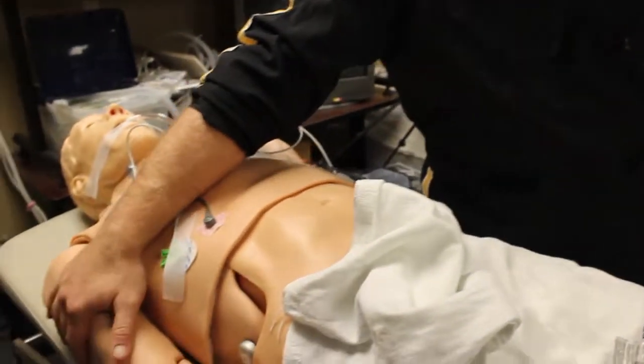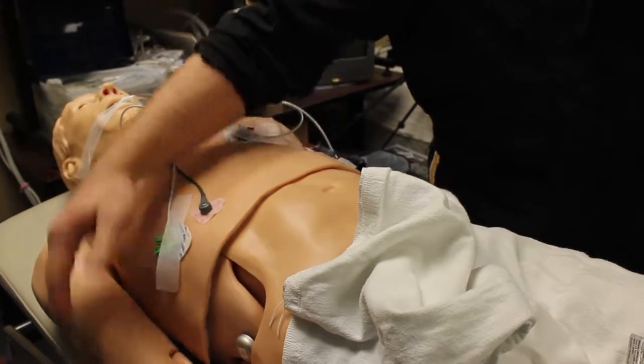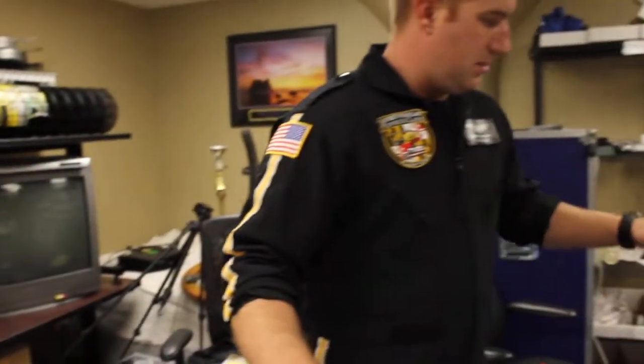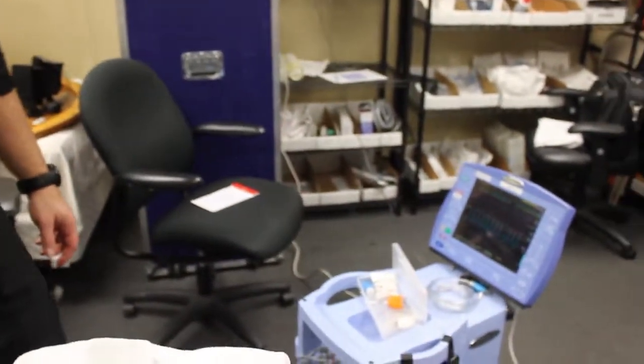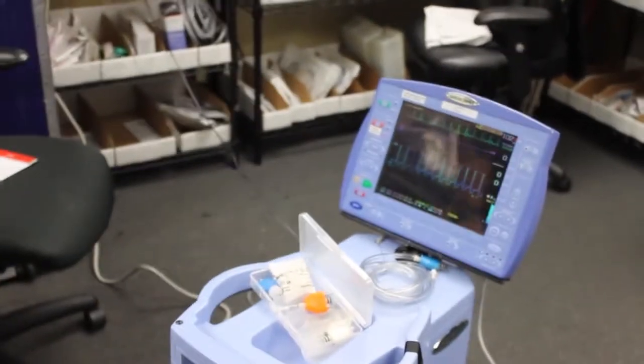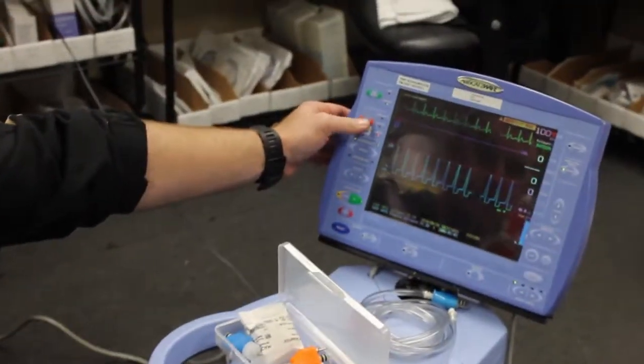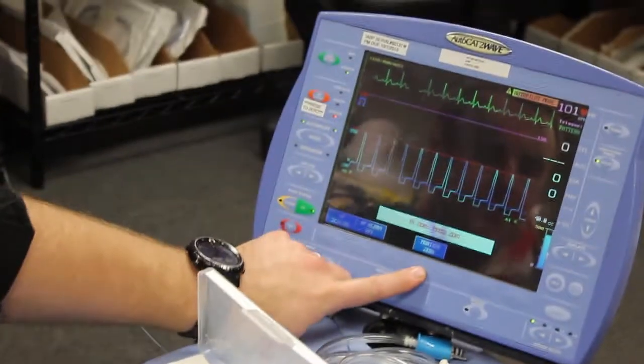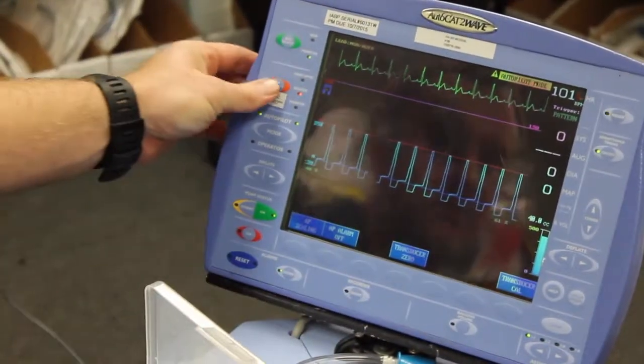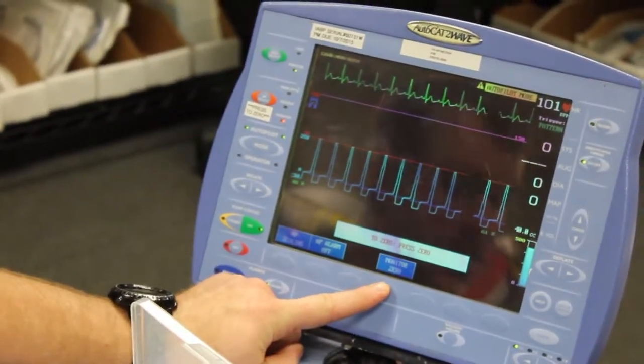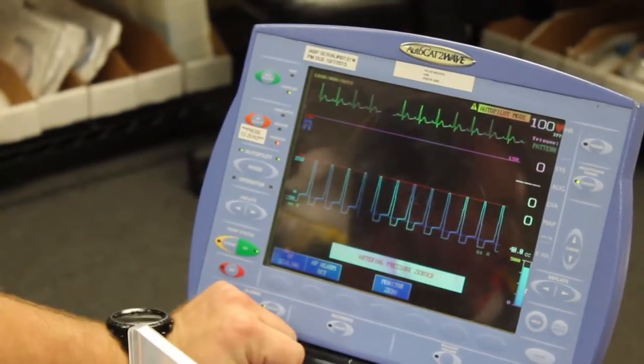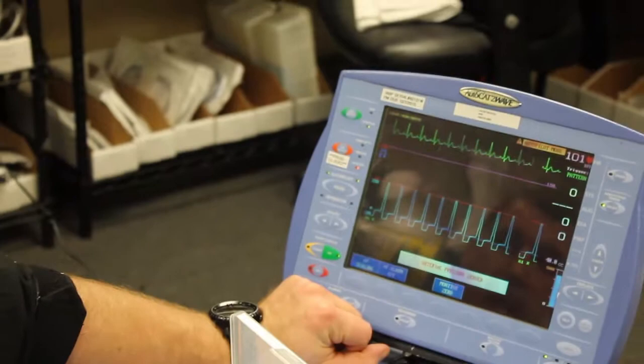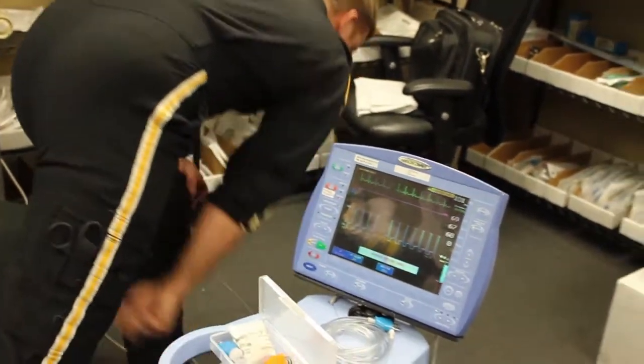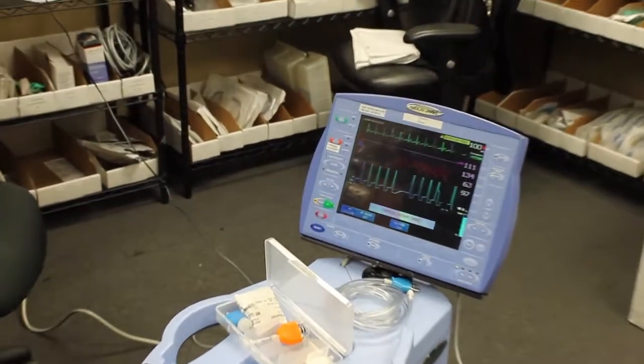Get your transducer positioned. Go ahead and move your transducer over. Typically, we'll tape it to their left arm, or the left chest. Then come back over to your balloon pump. Have your partner open up the stopcock like you're zeroing any other A-line, and with ours, we go ahead and hit the AP select. It'll say zero transducer. I'm going to go back to monitor because we're using the trainer, but it's in the same spot. You go ahead and zero it. It'll say arterial pressure zeroed. You flip the stopcock back like you do with every other A-line, and then you should get an AP source. So then you get your AP source.